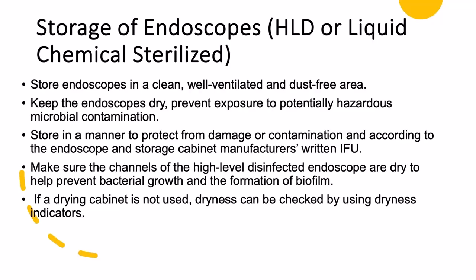Storage of endoscopes, high-level disinfected or liquid chemical sterilized. Store the endoscopes in a clean, well-ventilated, and dust-free area. Keep the endoscopes dry and prevent exposure to potentially hazardous microbial contamination. Store them to protect them from damage and contamination and according to the endoscope and storage cabinet IFU. Make sure the channels of your high-level disinfected endoscope are dry because you don't want bacteria to grow and for formation of biofilm. And if a drying cabinet is not used, dryness can be checked by using dryness indicators. As I mentioned, there's an annex that gives you a lot of guidance on that.